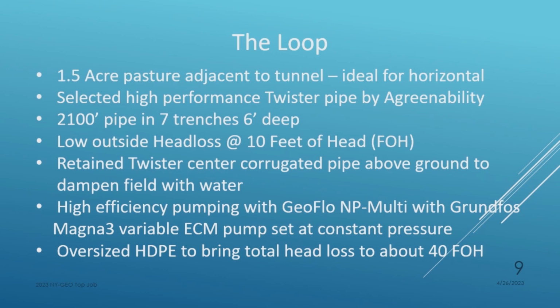We went with a nice GeoFlo NP multi, used the Grundfos Magna 3. It's a variable speed ECM. Set at constant pressure, so it didn't matter where the settings were on the various heat pumps or this water side economizer. The pump only spools up as much as you need. And basically, we were under 300 watts, which is 3% pumping. And when you rate a unit, you get a 10% budget. So we picked up quite a bit on pumping.